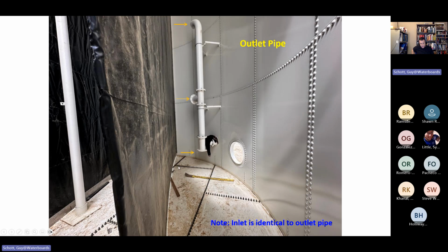The other concern is the bolts here. There's no good picture to see what it looks like under the bottom, but if you get a gap here from the bolts, you will get short circuiting under these baffles. So I wish that somebody had taken some pictures here so we could at least see what it looks like at the bottom, next to these bolts here.